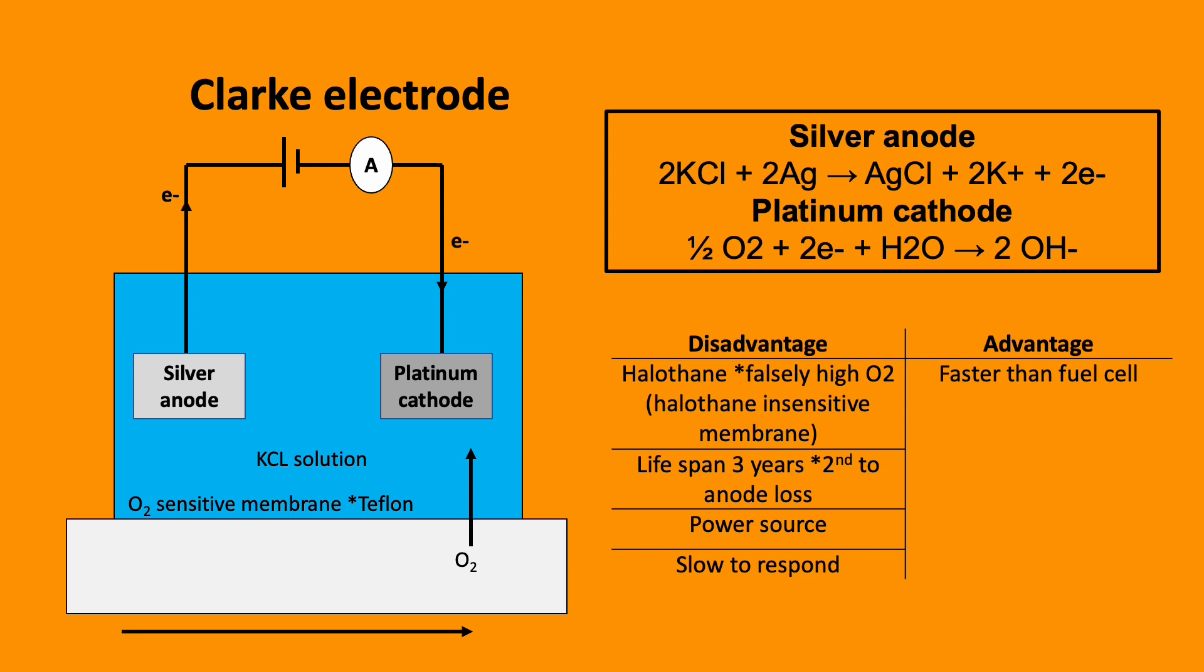Conversely, at the cathode, the platinum electrode acts as a catalyst reducing the dissolved oxygen in the sample. The oxygen diffuses via the O2-sensitive membrane into the potassium chloride solution and combines at the platinum cathode.